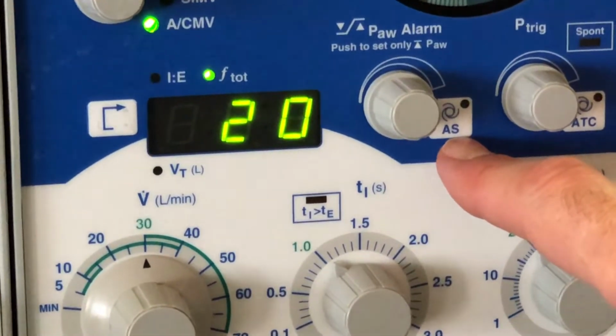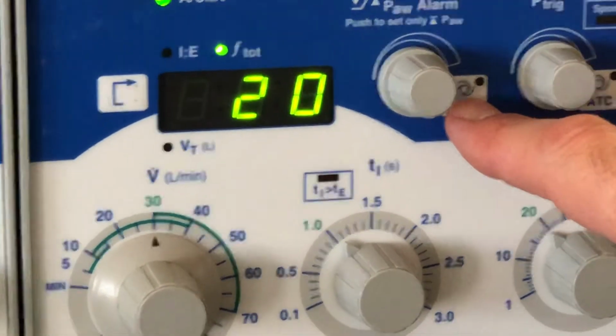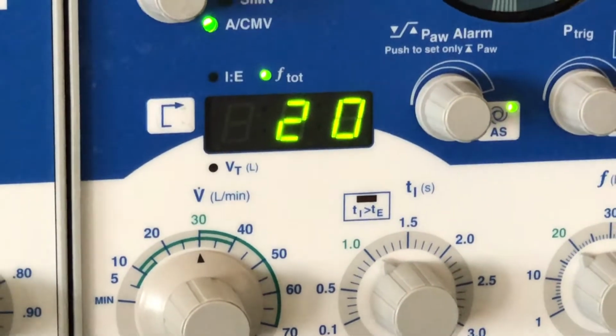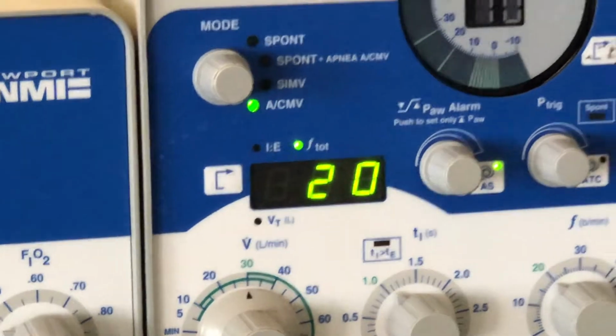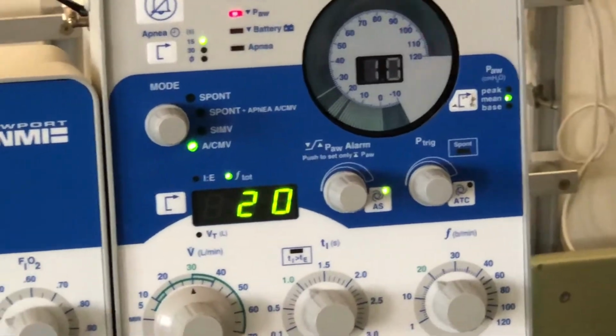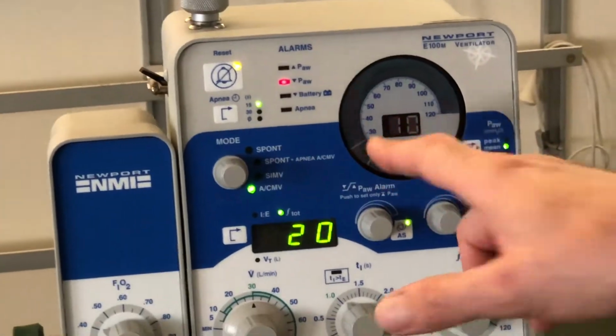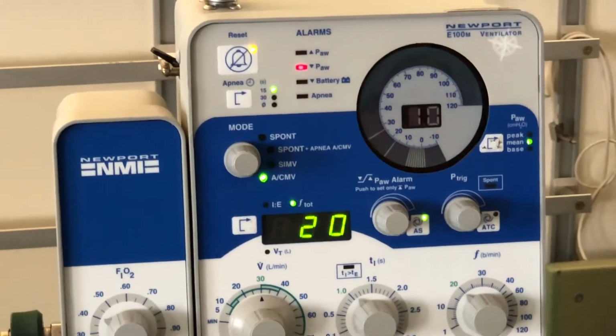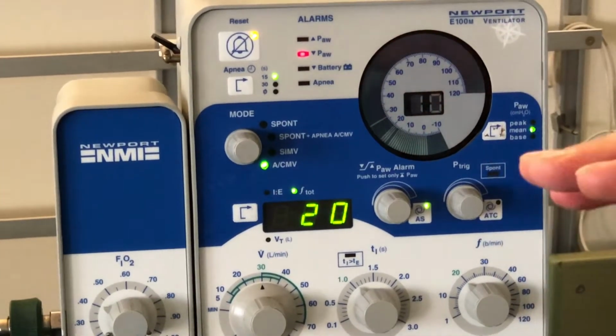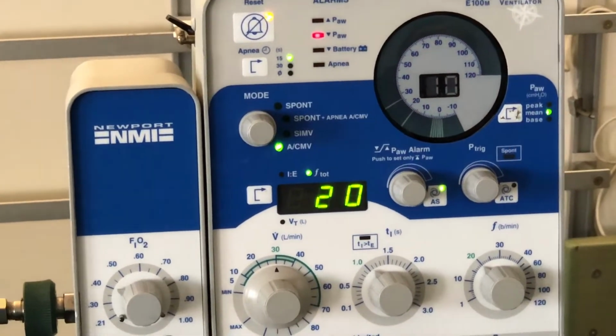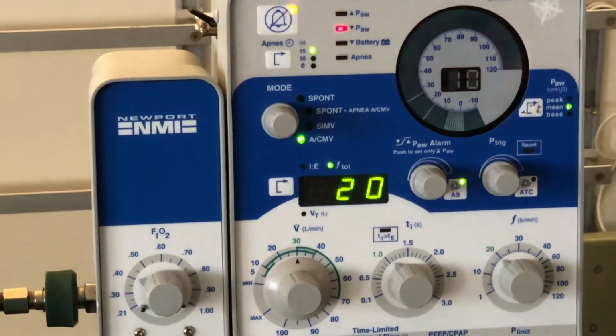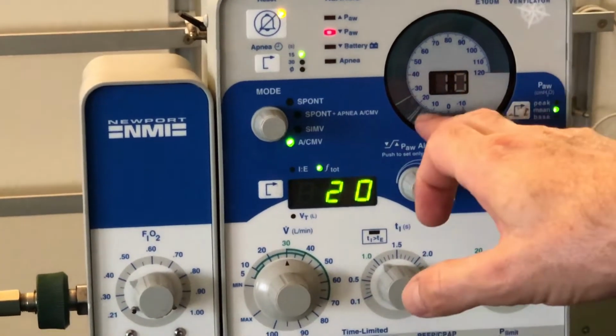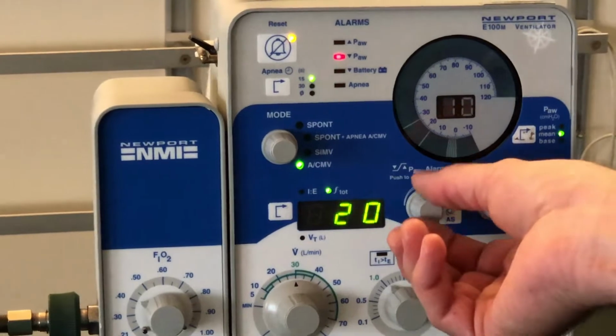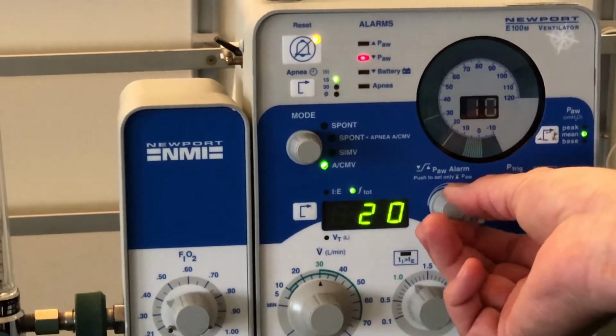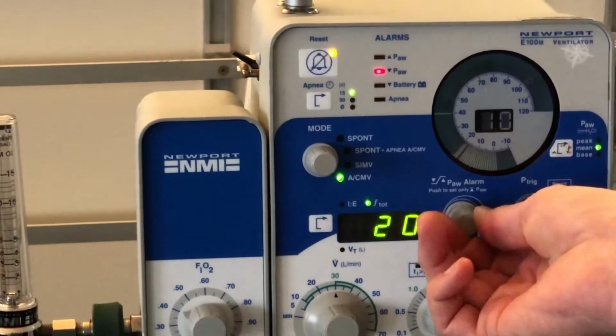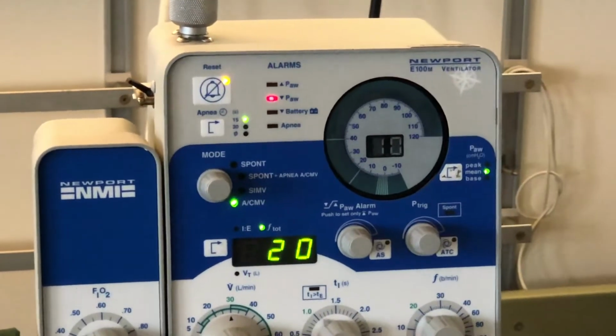Okay, that's the auto setting for the alarm limit. So if I push it, the machine will monitor a breath or two, and then it will adjust the pressure limits automatically. And there you can see it's done it. The one disadvantage of the automatic setting is it tends to make the upper airway pressure limit quite low. So once I've got the auto setting done for the lower pressure limit, it's useful just to push the dial in and raise the upper pressure limit to about 40 centimeters of water.